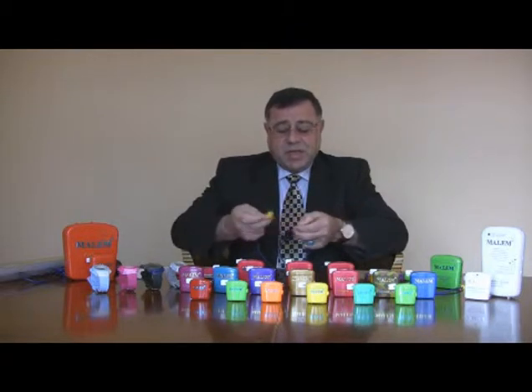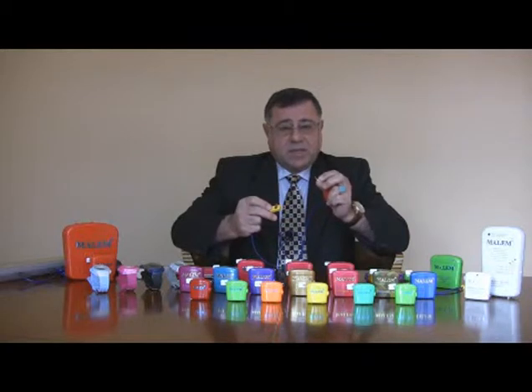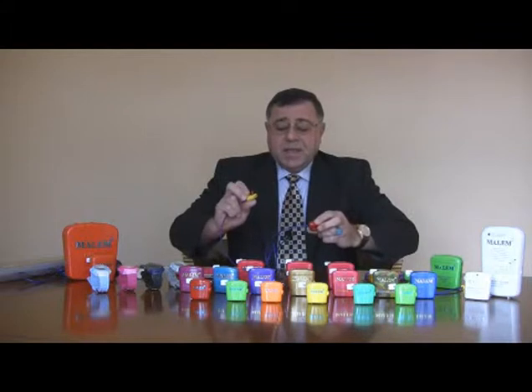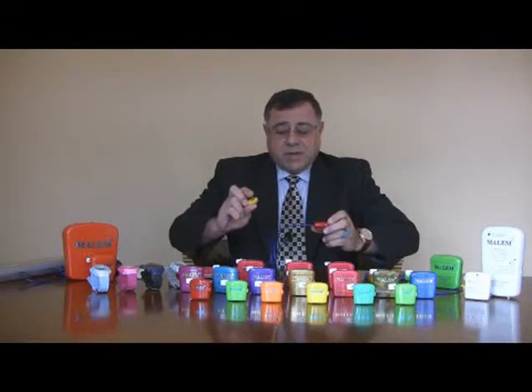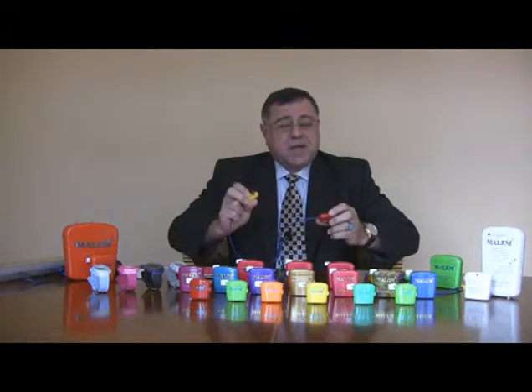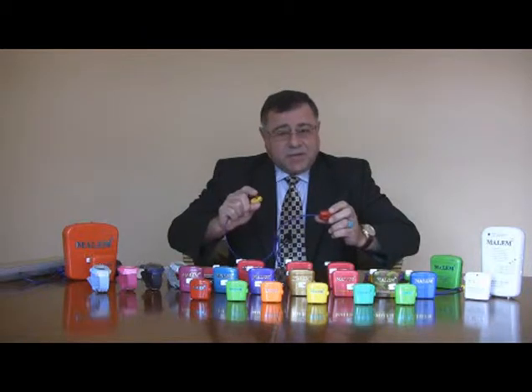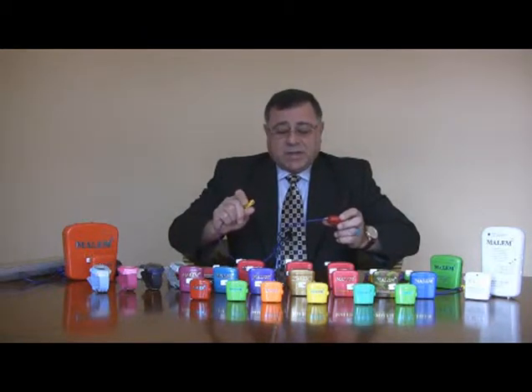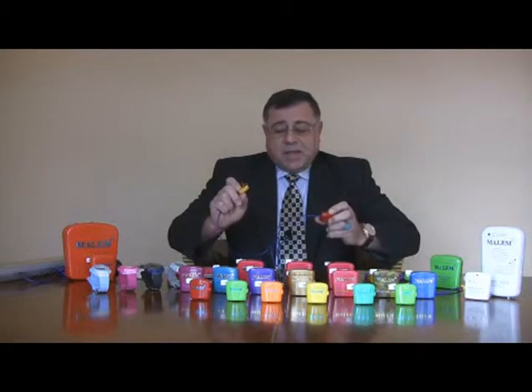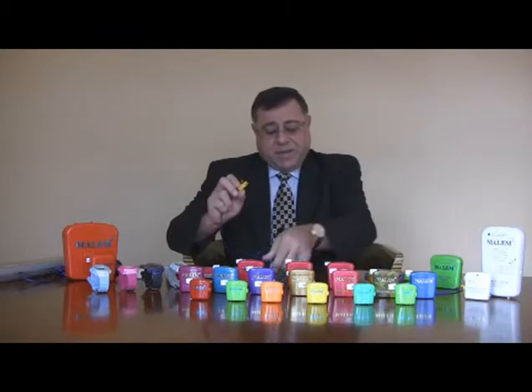At this stage, with the easy clip sensor, you lift the lever, you remove the insulator, and you do not need this insulator again. If unwittingly you lower the lever without the sensor attached, the alarm will go off and you will not be able to switch off the alarm unless you lift the lever. So lowering the lever, you will not be able to switch off the alarm. And the lever should only be lowered once it's attached to the underpants.